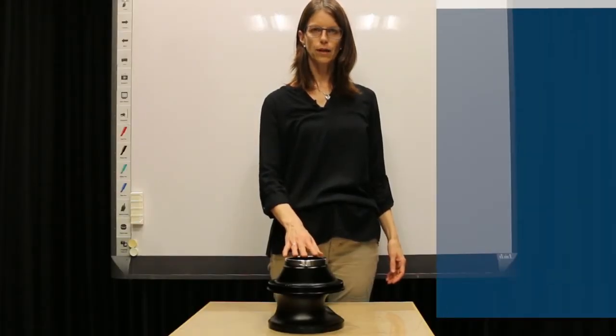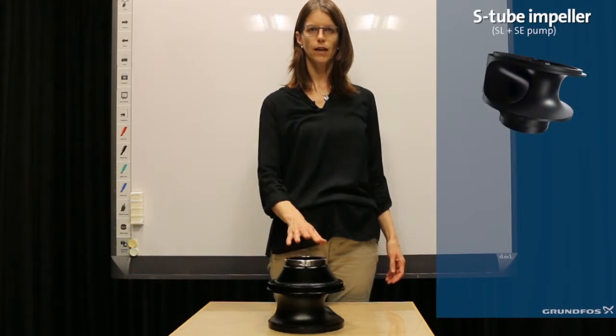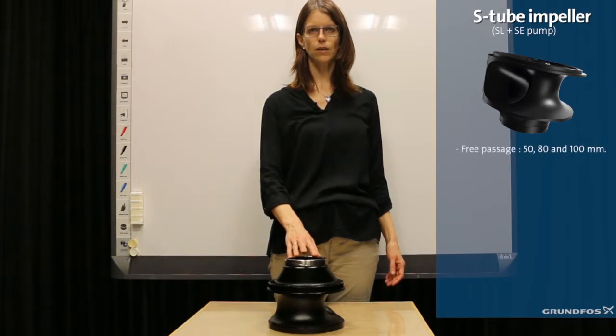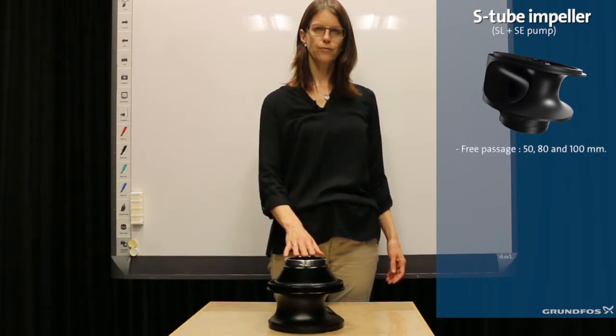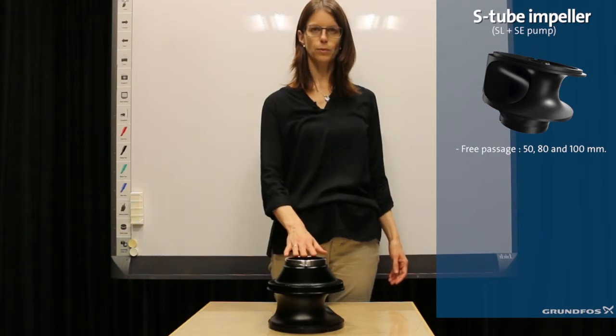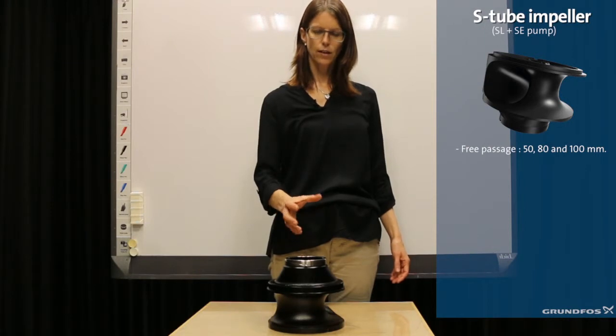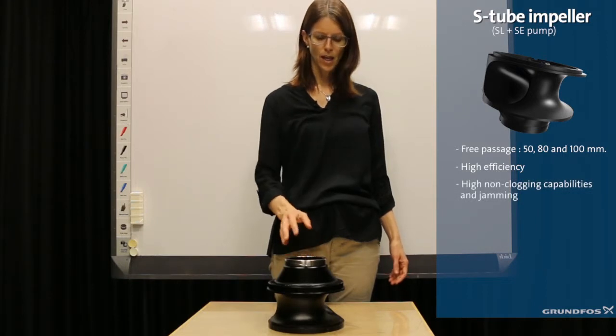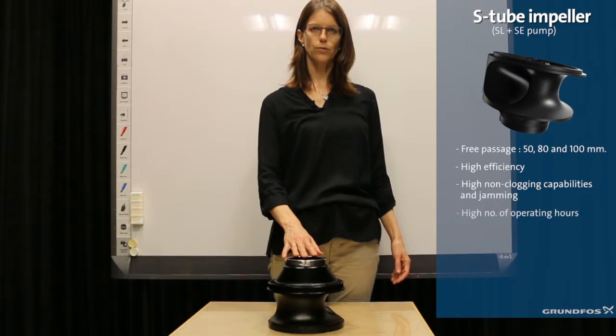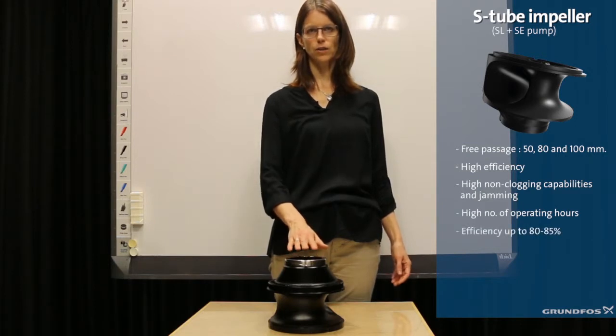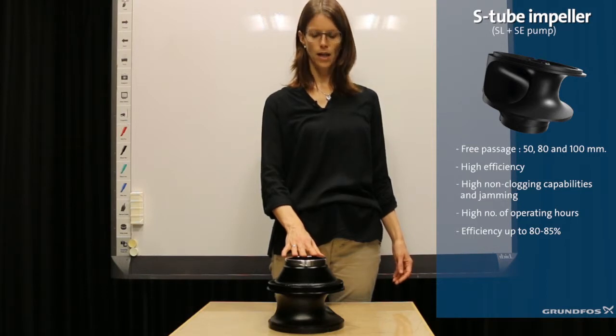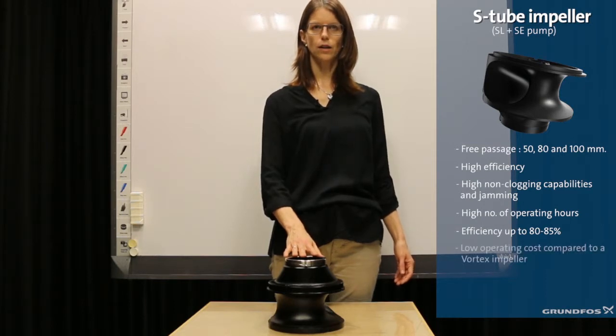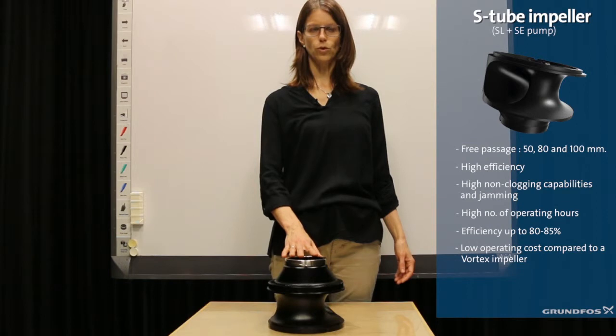Here you see the S-tube impeller offered by Grundfos. It is a closed impeller available with a free passage of 50, 80 and 100 millimeters. Grundfos has refined the original tube impeller design invented in the 1980s, achieving very high efficiency and very good non-clogging capabilities. This impeller is ideal when the operating hours of the wastewater system are high, because you can obtain a hydraulic efficiency of up to 80 to 85 percent, which means significantly reduced operating costs compared to a vortex impeller.